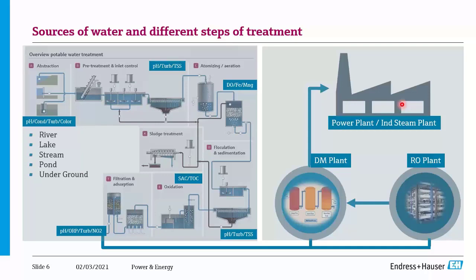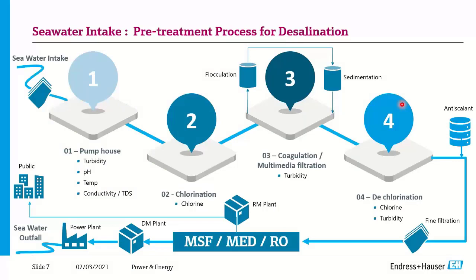For the other 95 to 96 percent of global sources — seawater — a different treatment process must be followed. At the seawater intake, the same basic parameters must be monitored: turbidity, pH, temperature, conductivity, and TDS. Once we know these, we can determine the disinfection required, because seawater contains a lot of bacteria and fungus. There will be a chlorination setup to neutralize those components.